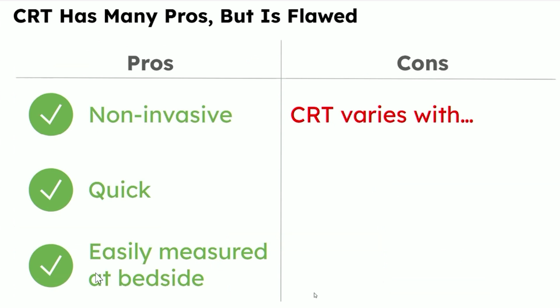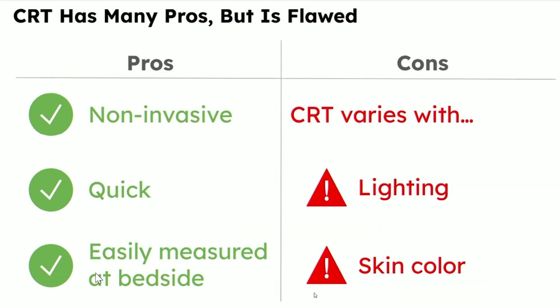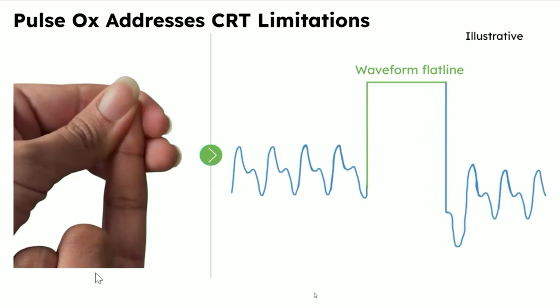However, manual CRT measurements are subject to significant variability, specifically in low light settings and in patients with different skin colors. Pulse ox can eliminate these shortcomings. This is a normal pulse ox waveform. When a patient's finger is compressed, the waveform flatlines. After compression is released, we can calculate the CRT as the time between the end of the waveform flatline and the return of the waveform baseline.